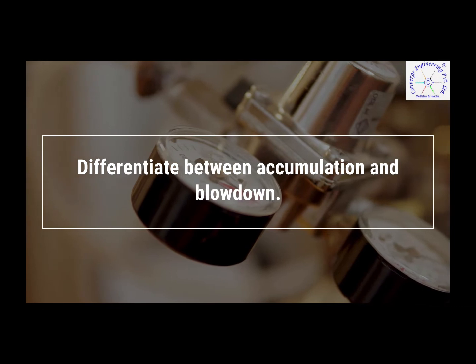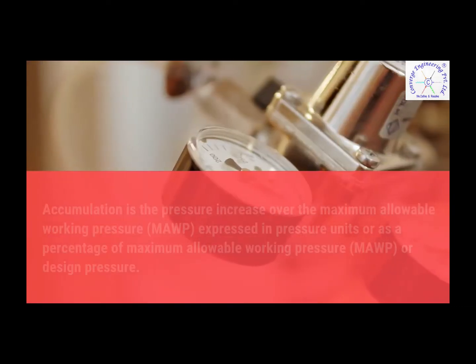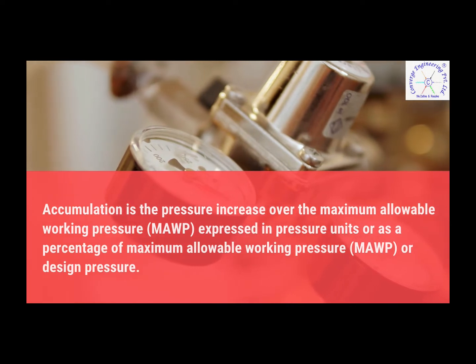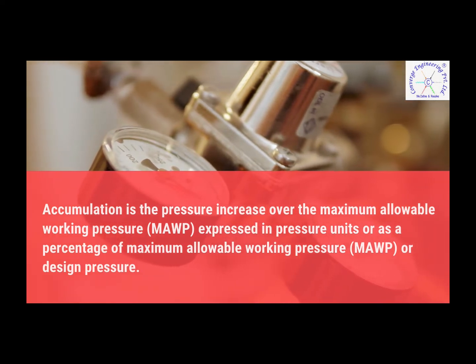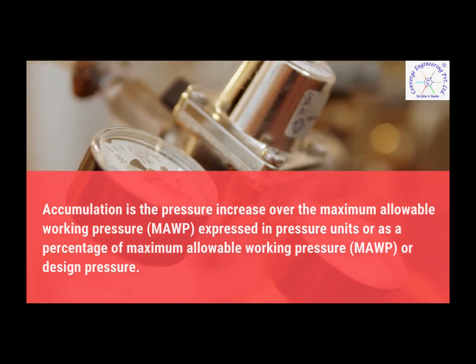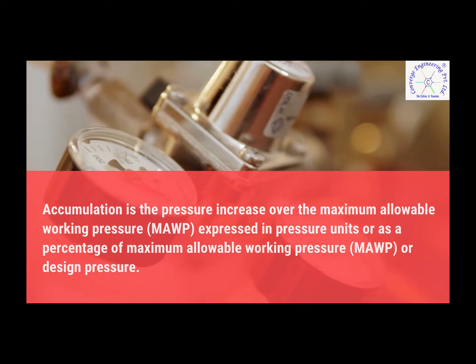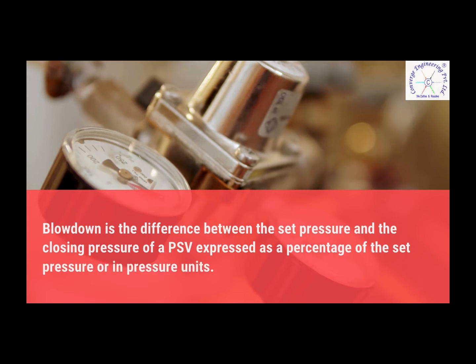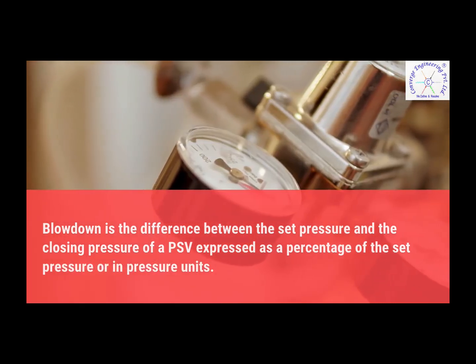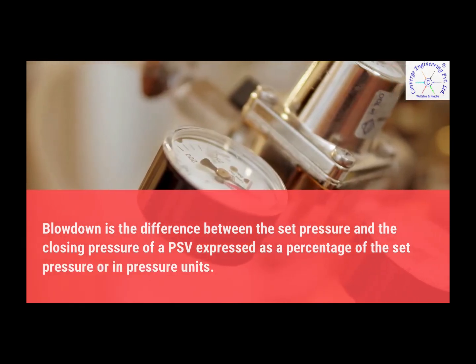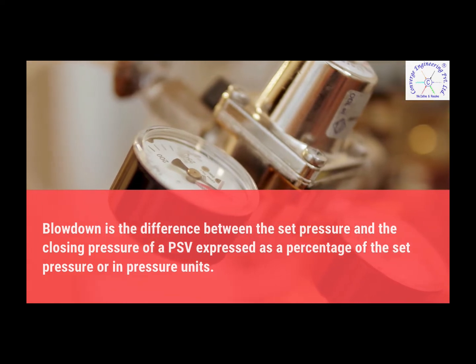Differentiate between accumulation and blowdown. Accumulation is the pressure increase over the maximum allowable working pressure, expressed in pressure units or as a percentage of maximum allowable working pressure or design pressure. Blowdown is the difference between the set pressure and the closing pressure of a PSV, expressed as a percentage of the set pressure or in pressure units.